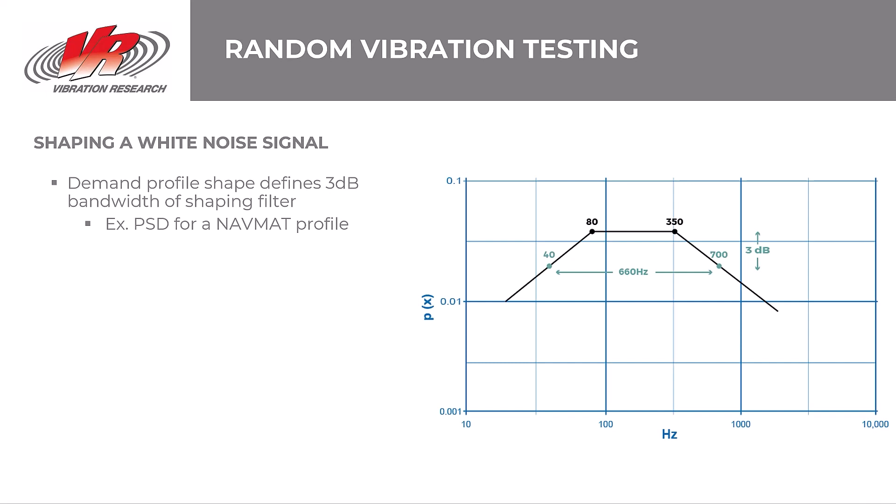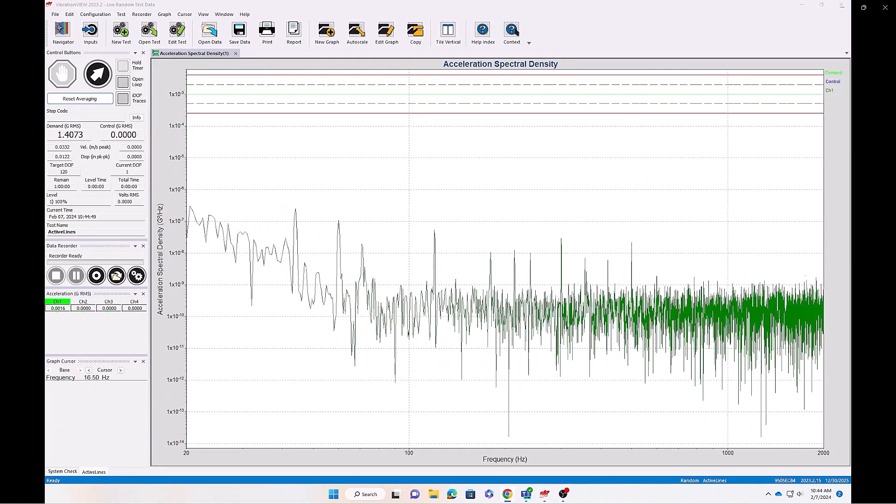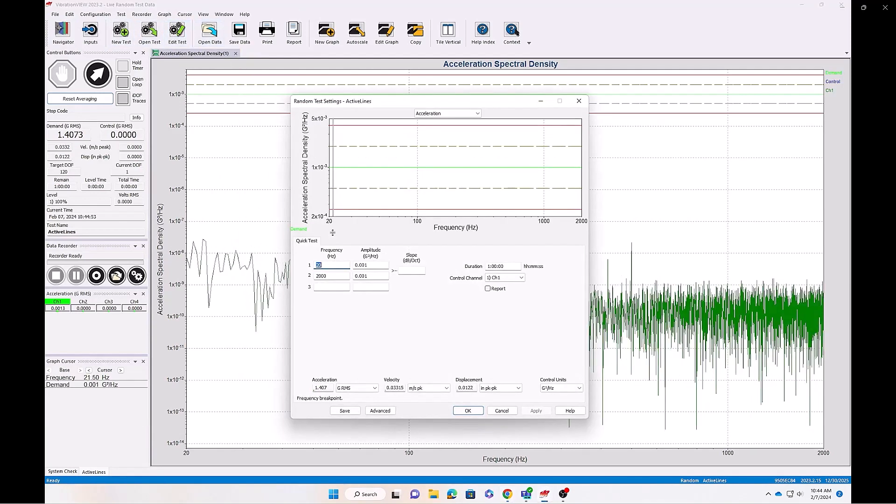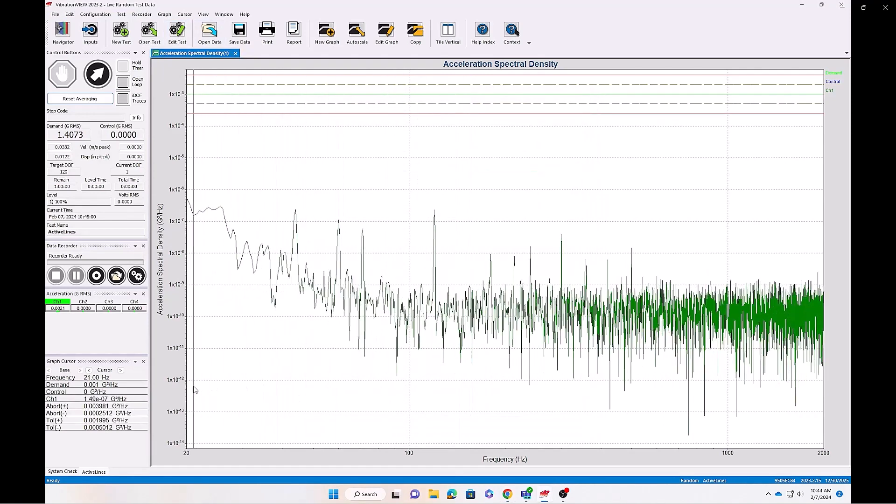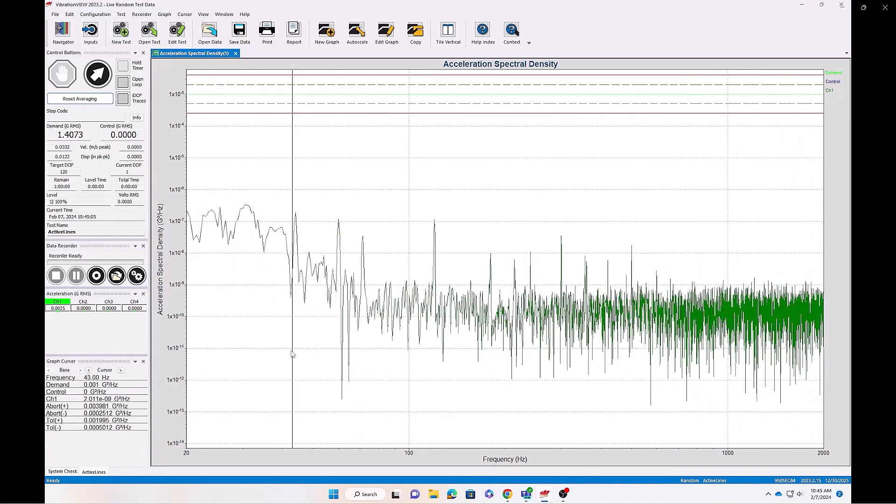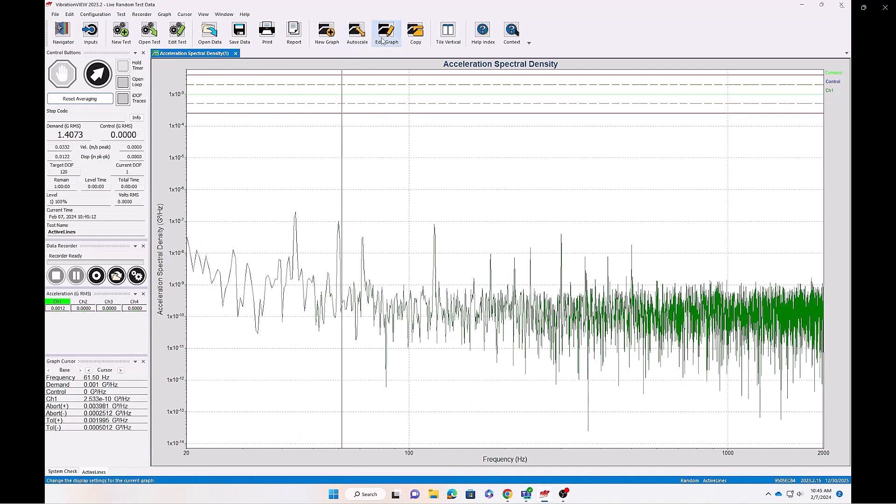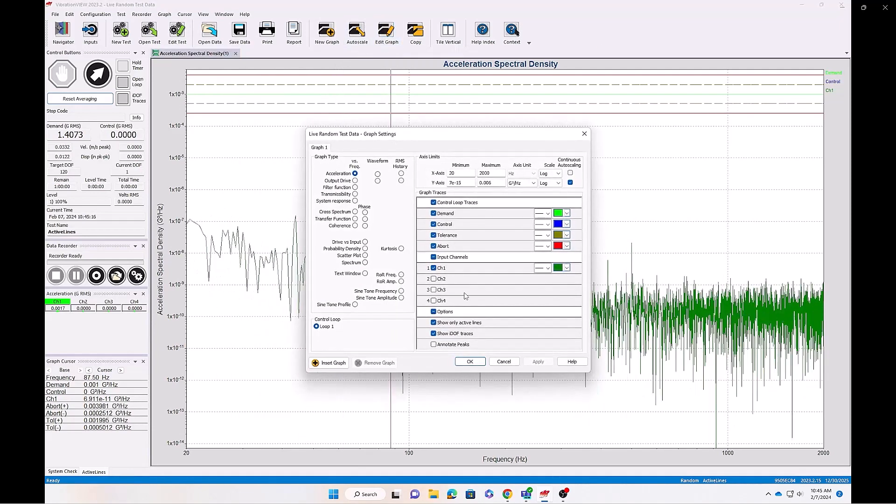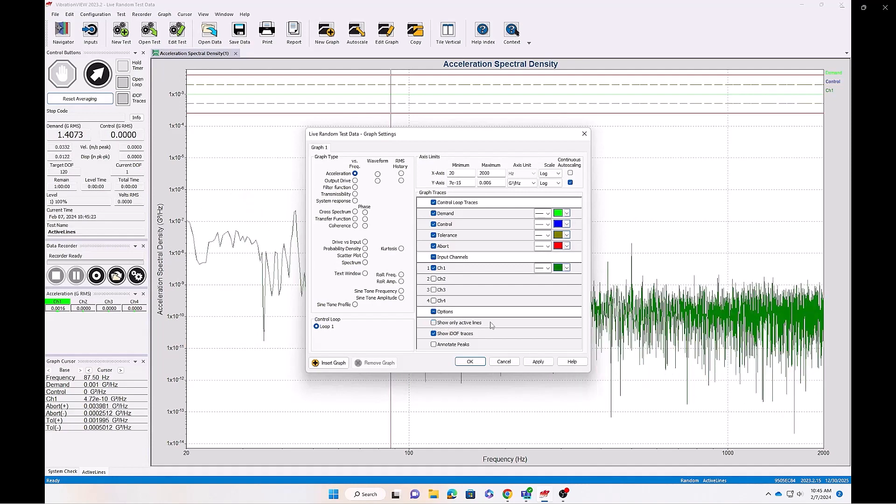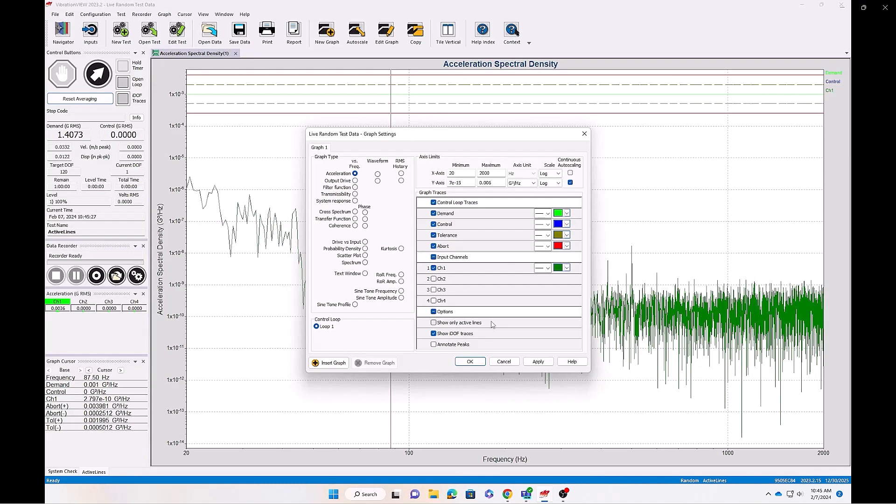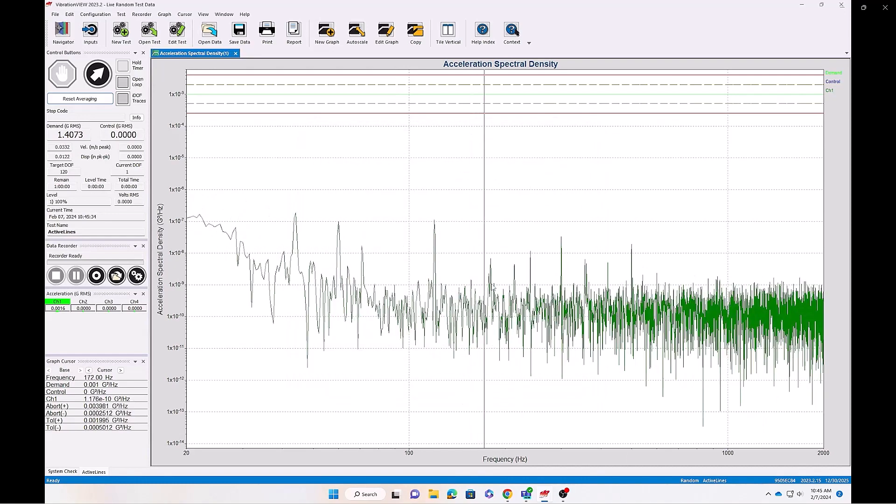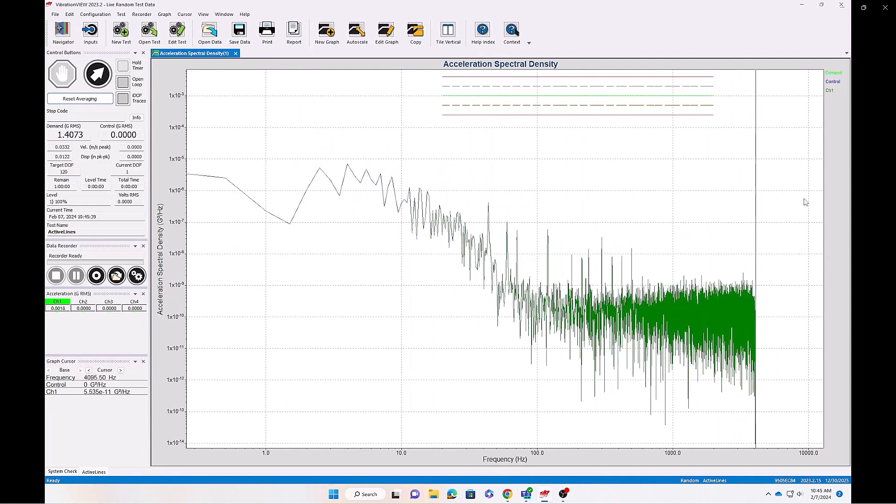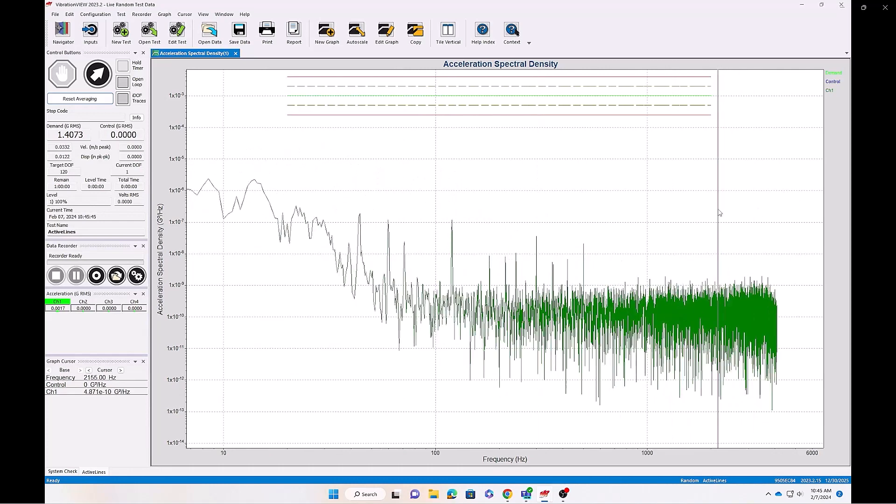Now, let's quickly look at the effect of our random resolution parameters. If I open a test profile in vibration view, we can view random data within the bandwidth from 20 Hz to 2,000 Hz. Technically, the engineer only needs to report on 20 to 2k, but it may be worthwhile to look outside this bandwidth. If I select Edit Graph and navigate to my options, I can deselect Show Only Active Lines. When we do that, we can review what's happening below 20 Hz and above 2k. Now, by default, our lines parameter is 800 at a one-time sample rate. And we can see a few lines outside the test bandwidth. These parameters act as a sort of filter by defining the frequency resolution.